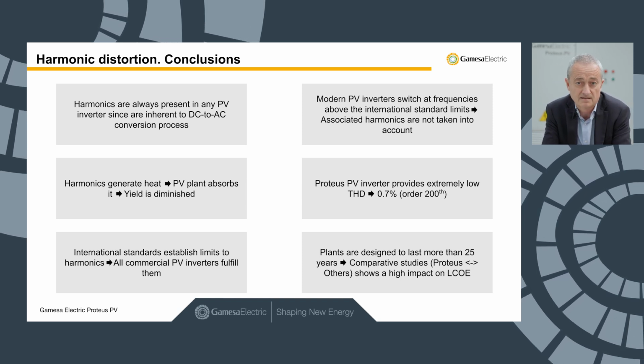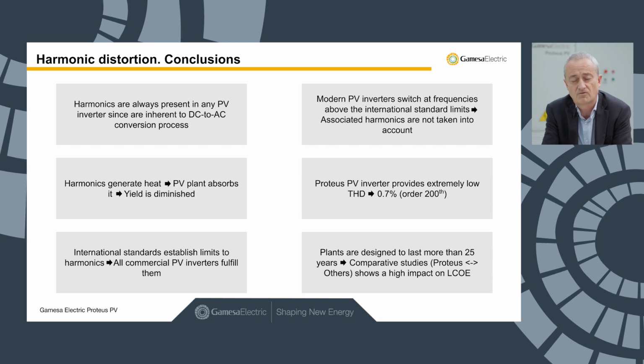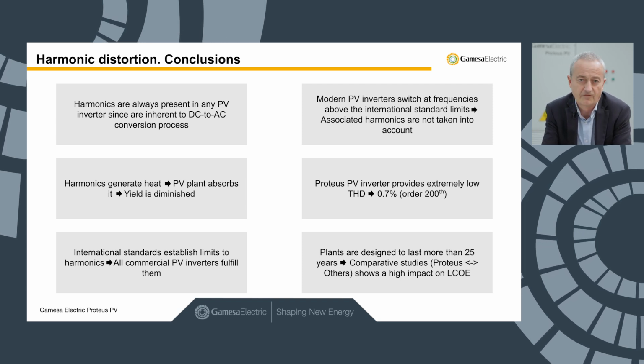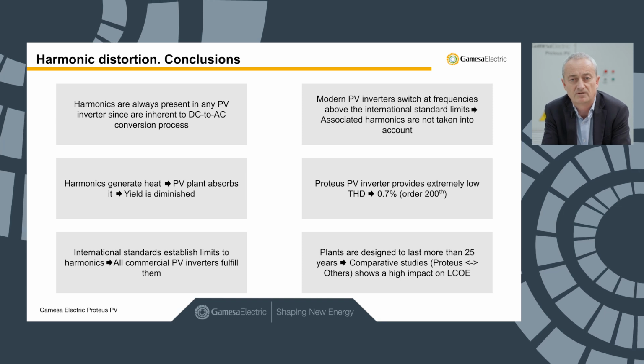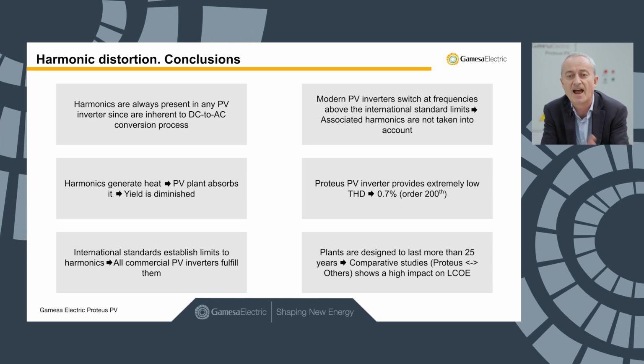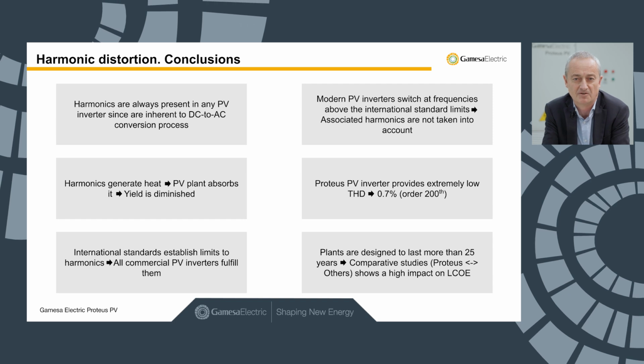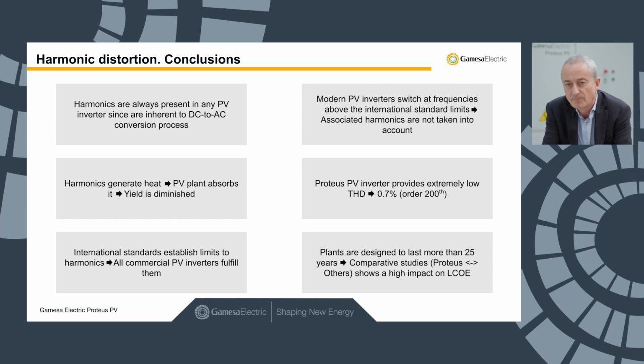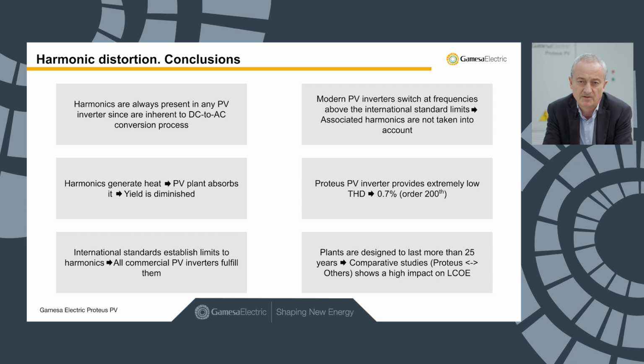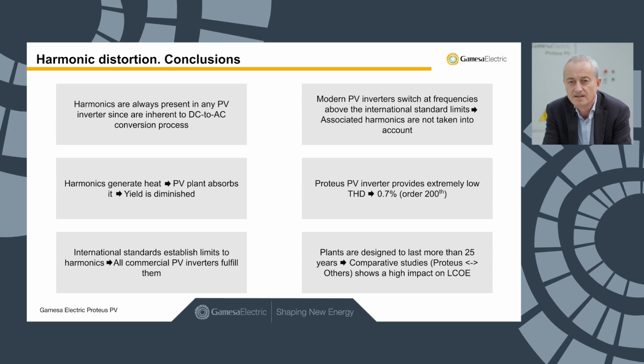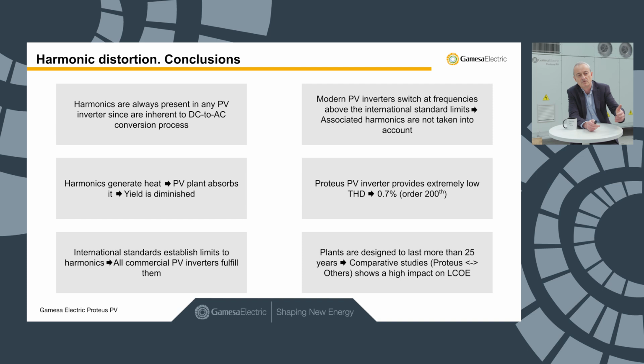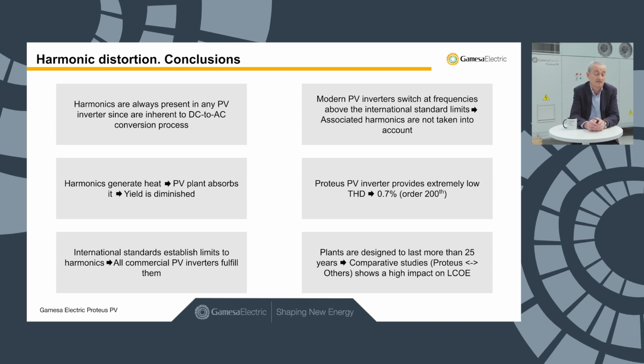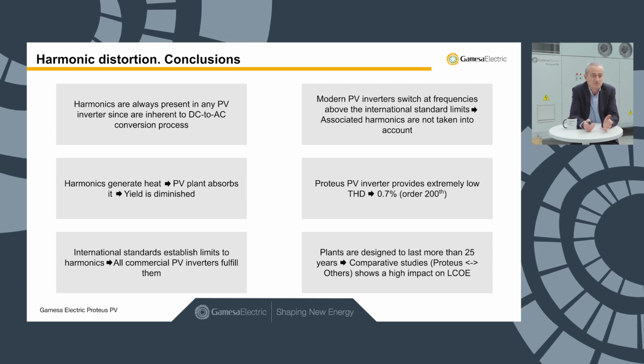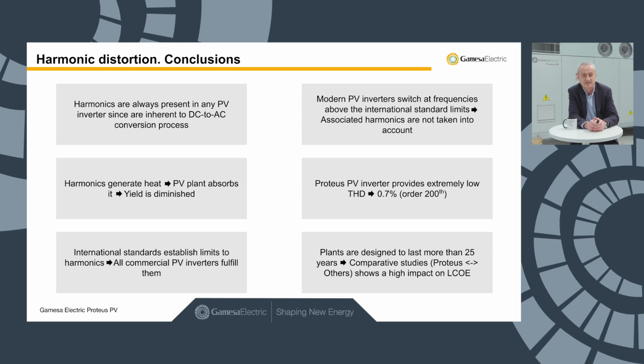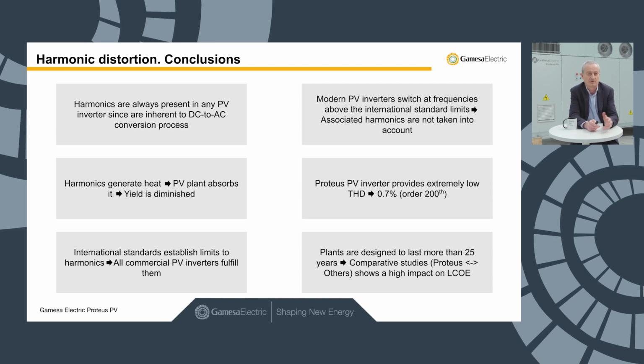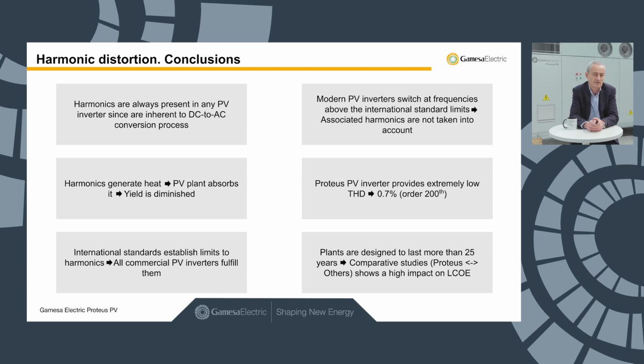There are standards, as my colleague has described, that have to be fulfilled, but the majority of inverters are switching at a frequency higher than the measurement of the standard. So it's extremely important to have a PV inverter with a THD well below the limits the standards indicate. And this is Proteus — the Proteus PV inverter is 0.7%, compared to the 3% that the standard describes.